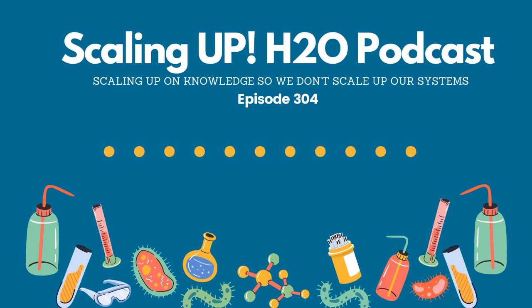So now you have to look at things where is it an issue with the operation of the system, or is it an issue with my actual water treatment program, or both? And then you need to talk with a customer. And if there's never any flow on a particular system, now we have all these systems here in Atlanta where they build out all these redundancies and they just run one chiller. And then they'll open up a chiller and they'll say, this chiller looks horrible.